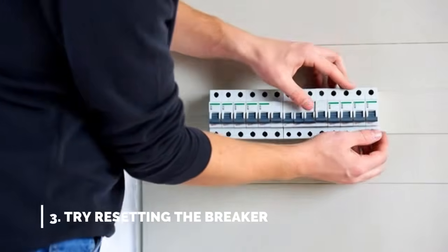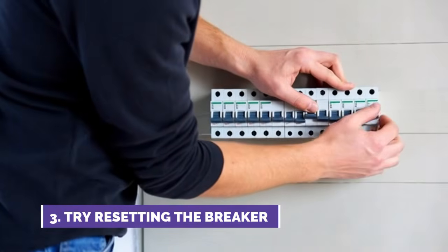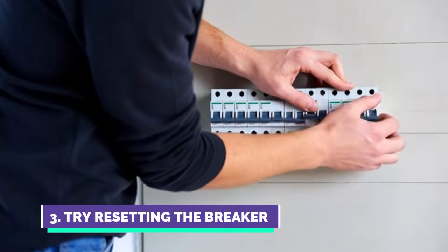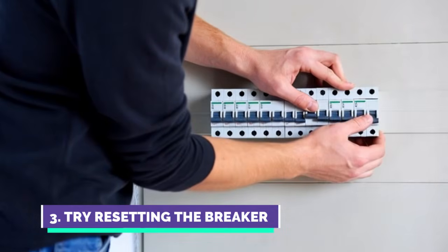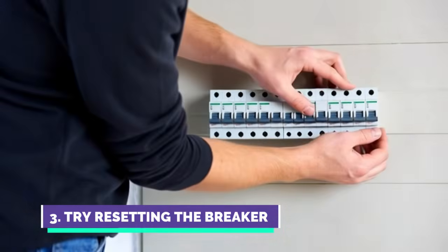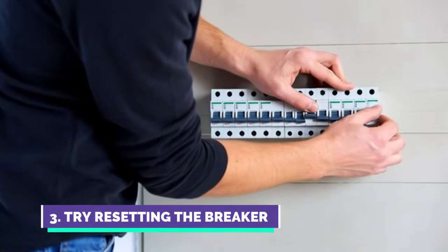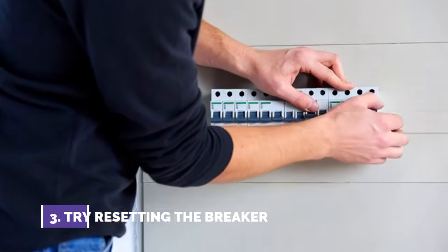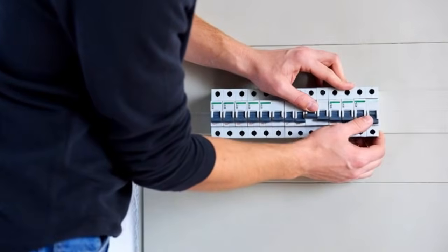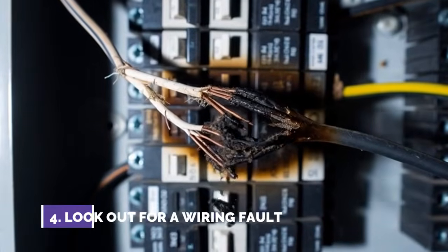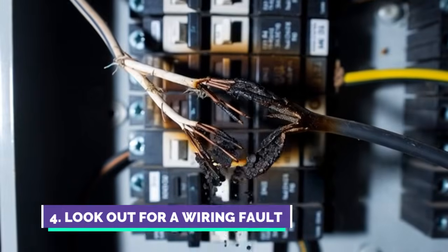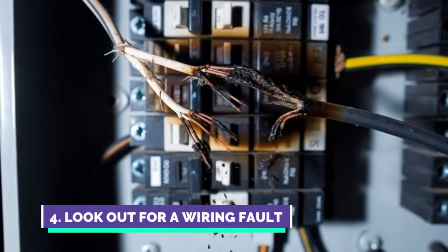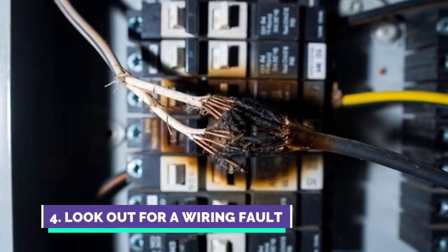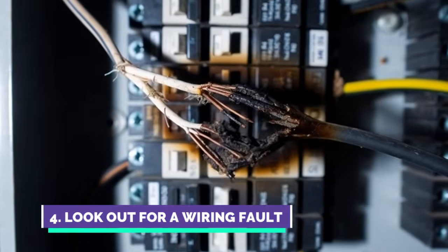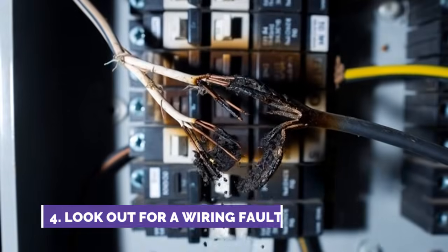Third, try resetting the breaker one more time with everything disconnected. If the breaker now resets and holds, the fault is likely in one of the devices you unplugged. You can reconnect them one at a time to identify the culprit. When the breaker trips again, you've found your problem device. Fourth, if the breaker still won't reset with everything unplugged, the fault is in the wiring itself, somewhere between the panel and the outlets. This requires professional diagnosis. Do not attempt to trace wiring faults yourself unless you're qualified to do so.